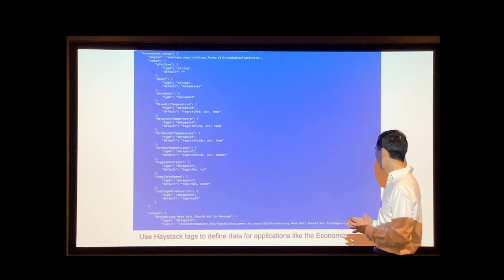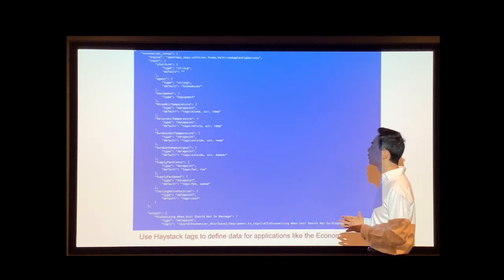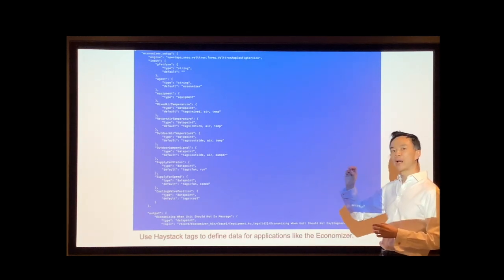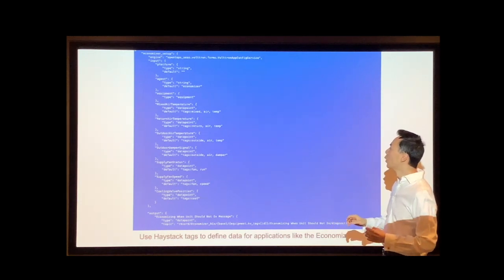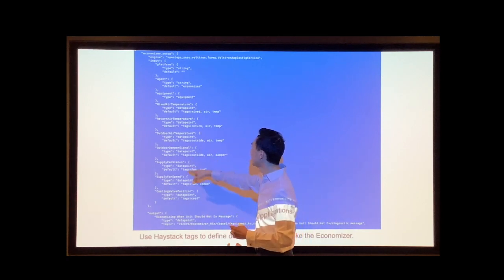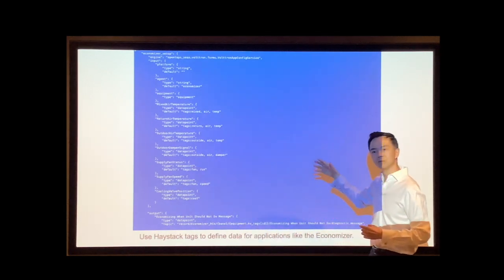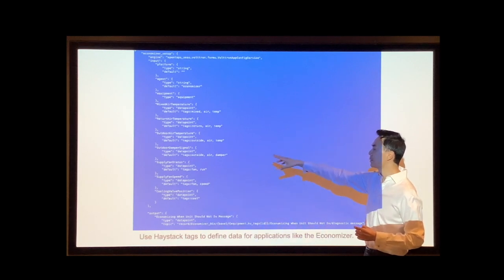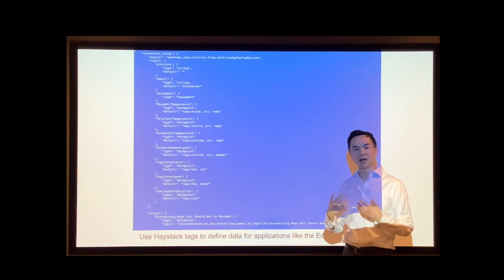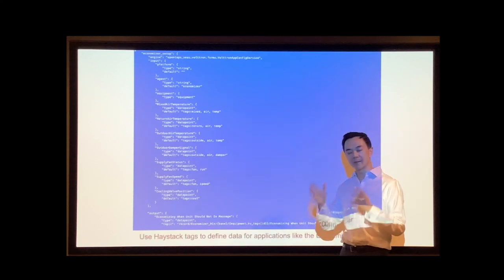Finally, this is something I think will be really important: the ability to define services and run applications using tagged data. This is for something called the Economizer from the VOLTTRON Applications Repository. What we did is replace all the parameters for data points in the Economizer app with Haystack tags, and then define it as a service in JSON format specifying what each parameter's tags should be. We have a service runner which will go out and find the data points based on those tags and feed them into the Economizer and run it. So apps in the VOLTTRON applications — like the Automated Recommissioning, Intelligent Load Control, Fault Detection, Economizer — could all be configured to run automatically for all different equipment at all different sites using this architecture.